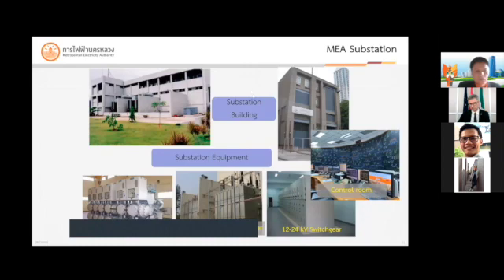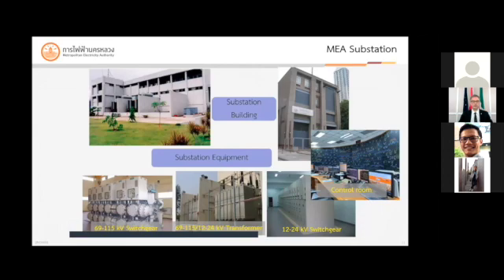MEA substation is actually similar to terminal stations in the previous slide, but it is smaller with different voltage level and is responsible for transmitting power to feeder line. It consists of substation building and substation equipment as well, with higher switchgear and lower switchgear and the transformer in the middle. That is 69 or 115 kV switchgear. The transformer in the middle steps down the voltage from 69 or 115 kV to 12 or 24 kV and 12 or 24 kV switchgear.